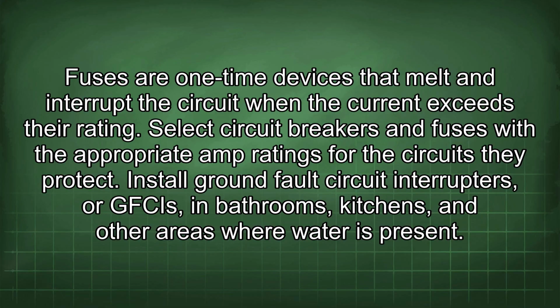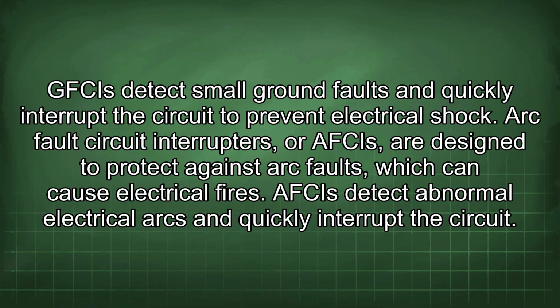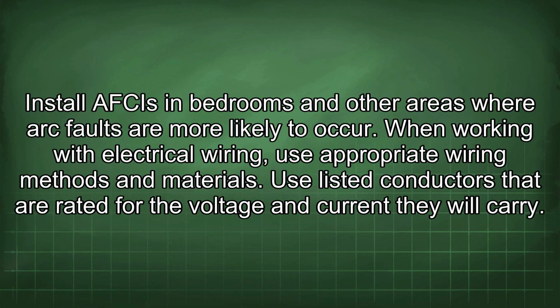Install ground fault circuit interrupters, or GFCIs, in bathrooms, kitchens, and other areas where water is present. GFCIs detect small ground faults and quickly interrupt the circuit to prevent electrical shock. Arc fault circuit interrupters, or AFCIs, are designed to protect against arc faults, which can cause electrical fires. AFCIs detect abnormal electrical arcs and quickly interrupt the circuit. Install AFCIs in bedrooms and other areas where arc faults are more likely to occur.